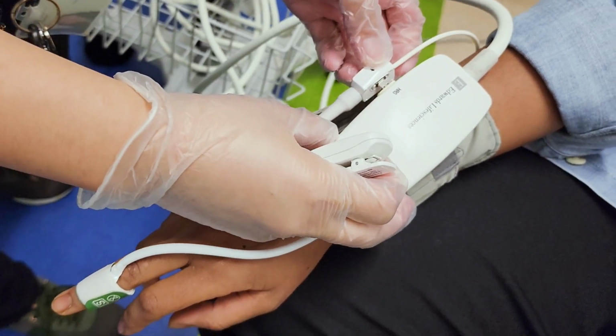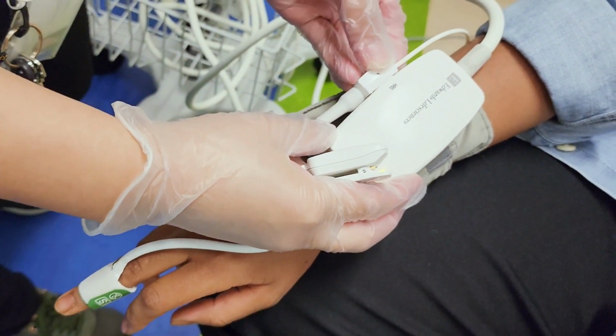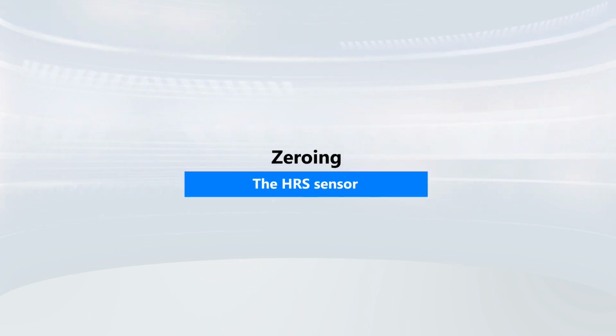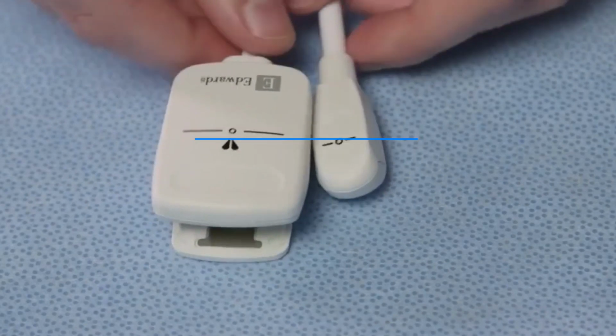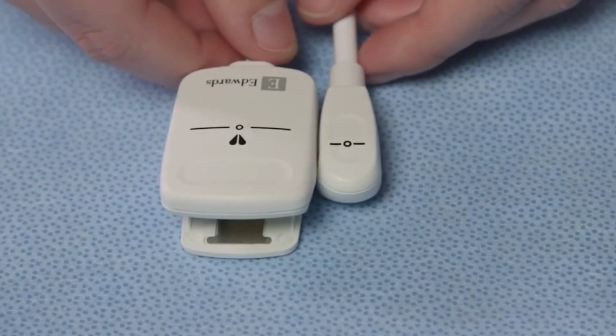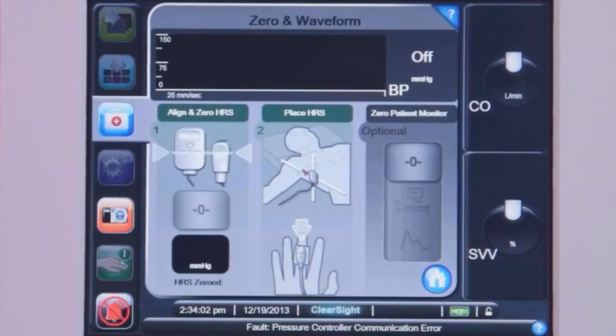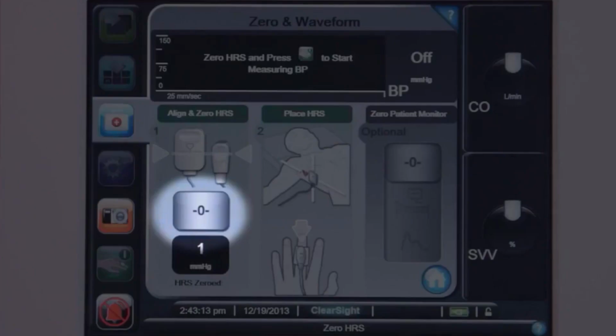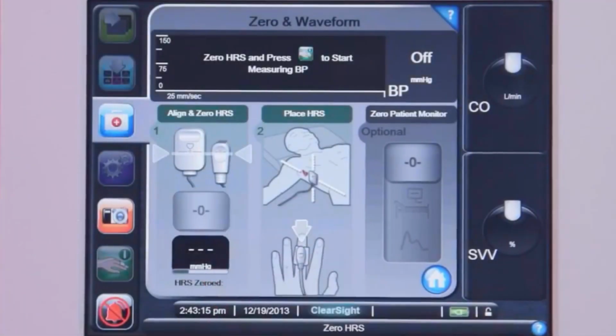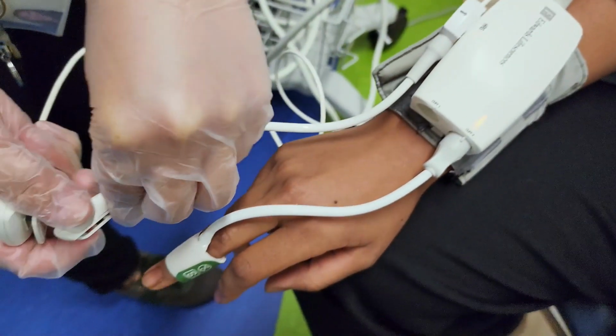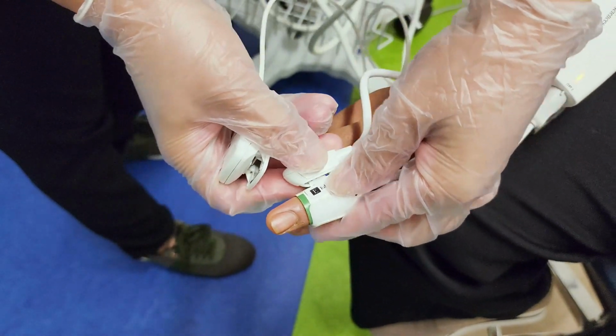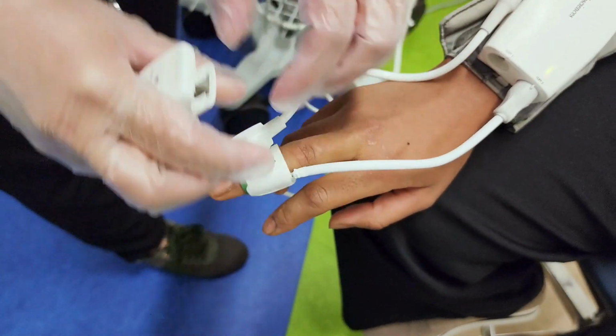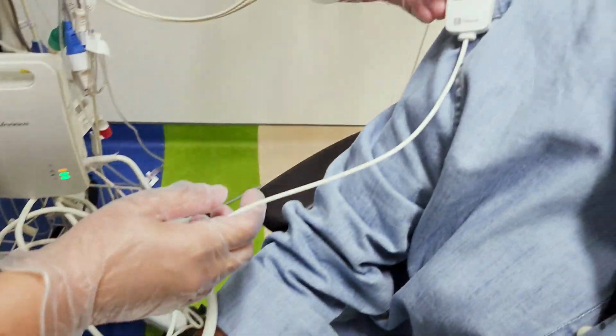Attach the heart reference sensor, or HRS, to the pressure controller. Place both ends of the HRS sensor at the same vertical level. Touch the clinical actions and choose zero and waveform. Tap the zero button under Align and Zero HRS. Attach the finger end of the HRS to the ClearSight finger cuff. Touch the heart end of the HRS to the patient at the phlebostatic axis.